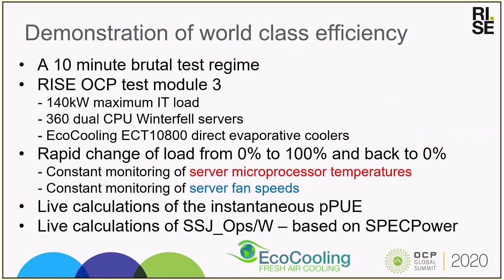So we're going to run a demonstration of world-class efficiency. It's going to be a 10-minute brutal test regime on this module, where the maximum power that the IT load draws is 140 kilowatts. We're going to do a rapid change of load, ramping up from 0 to 100% and then ramping back down. Then we do a square wave where we go from 0 to maximum power, 140 kilowatts, and then back down again, to see how the cooling system responds to this workload.